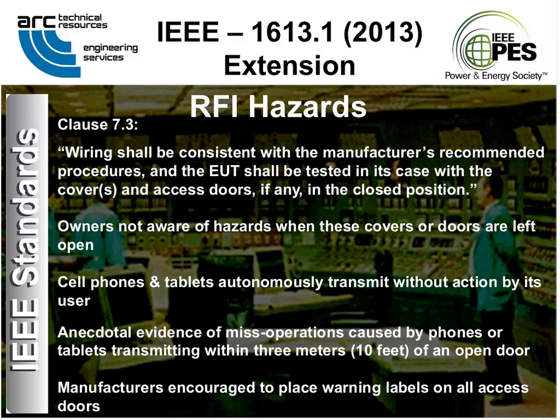We also included something from all those horror stories I told you up front. We called Clause 7.3, RFI hazards, informative. This was the one paragraph we took out from normative. It says that your wiring should be consistent with the manufacturer's recommended procedure, and the EUT should be tested with the covers closed. By the way, it should be operated with the covers closed too, as you've seen from the horror stories I told you earlier. Apparently, some owners of this equipment aren't aware of the hazards that can be exposed when the doors are open. I've shown you a few.